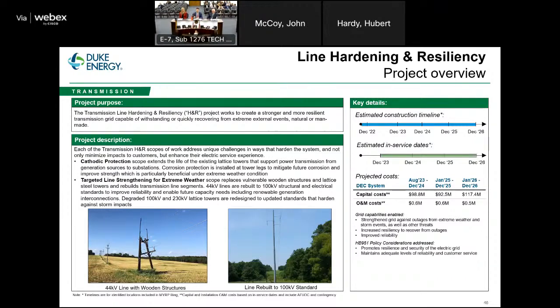In addition to individual locations on the 44 kV system, specific line segments that are particularly problematic historically for outages are targeted for rebuild, actually rebuilding that 44 kV system to the 100 kV standard. So in addition to replacing poles with steel, we're elevating the lineup — you can see the height difference between the two pictures, with the right showing a rebuilt 44 kV system to the 100 kV standard: higher poles, larger insulation, larger space.